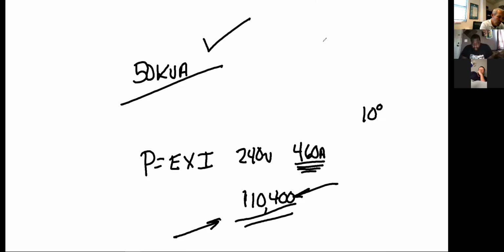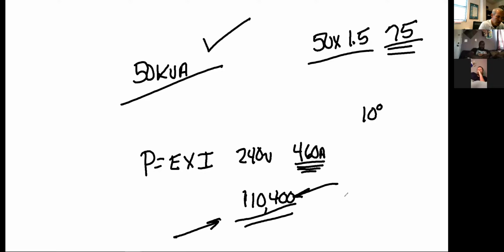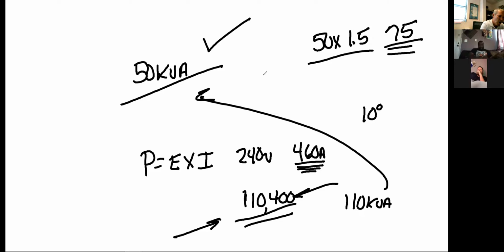110,400. It will not meet the overload situation, which is 50 times 1.5 - 150% only takes it to 75. It's still over that, it's 110 kVA. By your readings right here, it's time to change the transformer out to what?